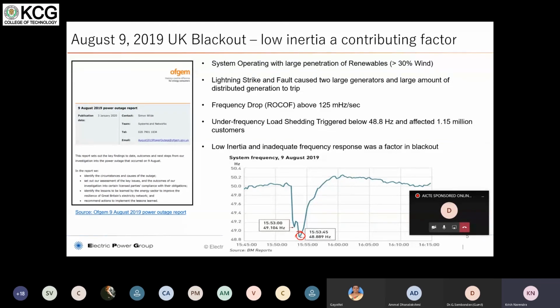Now, as a consequence of this, Great Britain appointed a task force to assess the inertia response of frequencies using synchrophasor data, because they wanted to know if the changes of dispatch and renewables connected to the grid are changing rapidly, by the very nature of the availability of the fuel, which is the sunlight as well as the wind in this case. These are very variable, and forecasting for that system is a very challenging thing even today. So it's important for operators, system planners, and protection engineers to understand the inertial response of the modern grid with embedded generation such as wind, solar, battery backup, and small hydro plants.